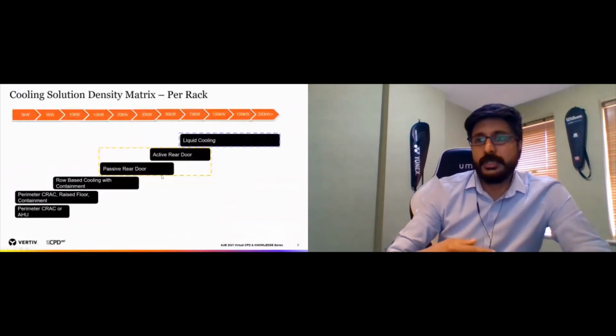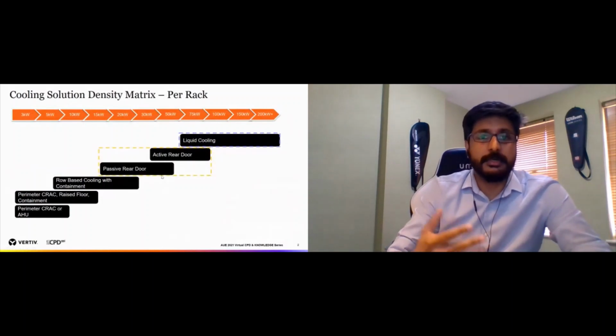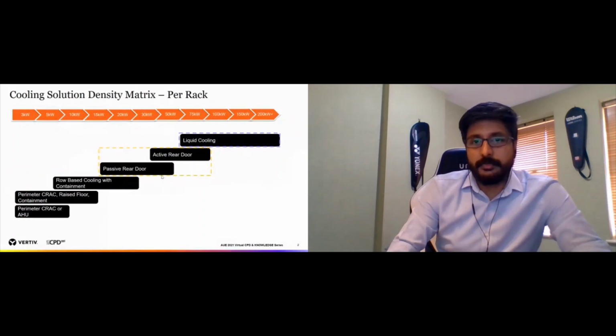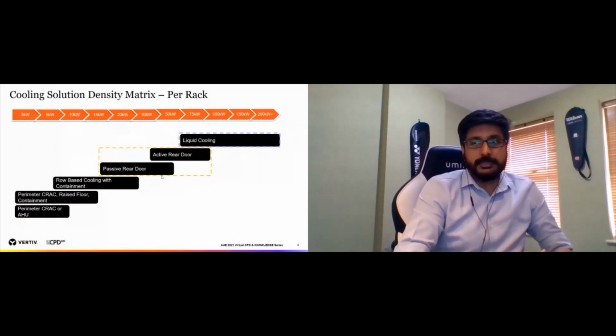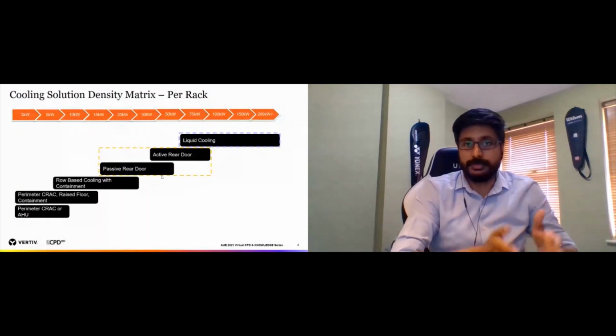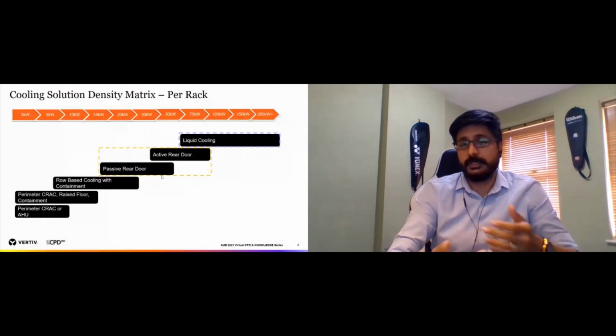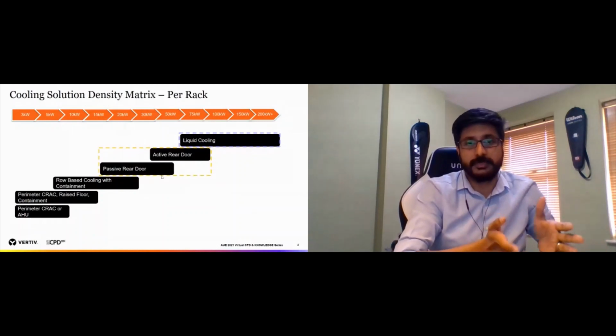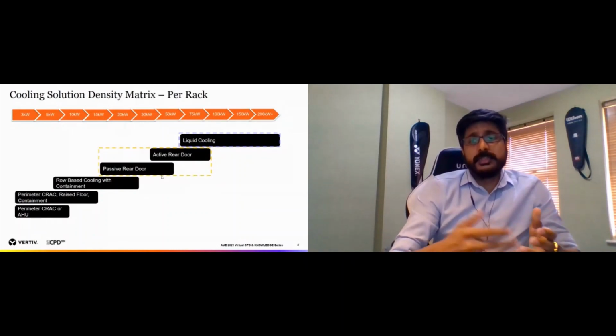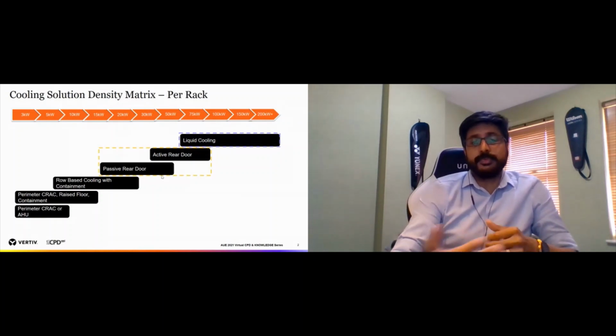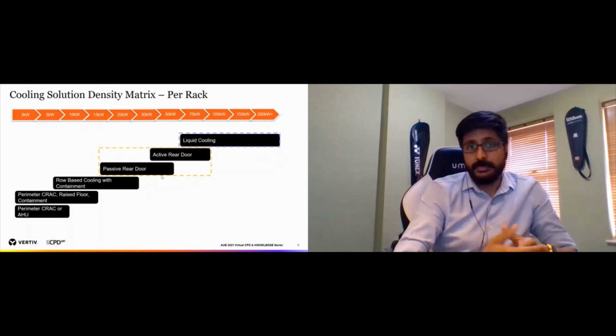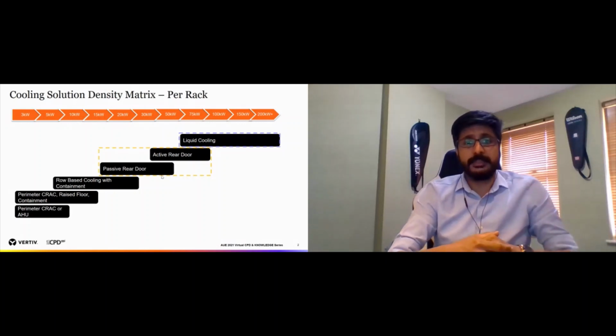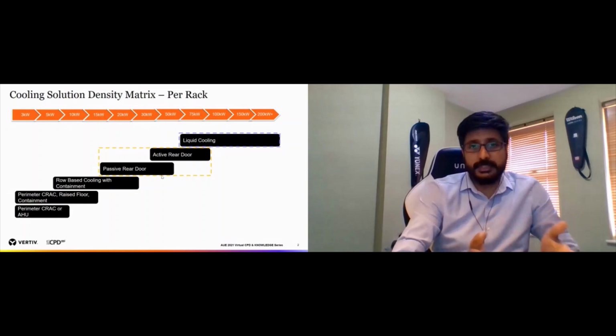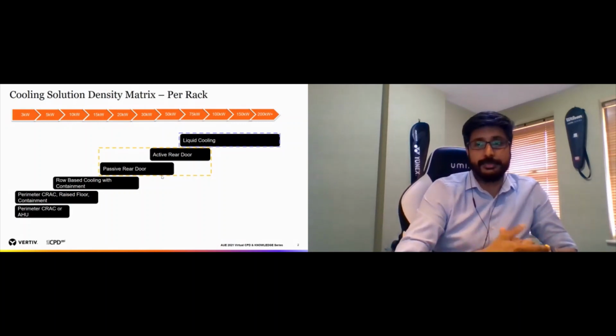As a rough calculation of how the cooling's been distributed, up to 3 to 10 kilowatts, we look into perimeter CRAC cooling solutions. Around 30 kilowatts of cooling, we think about row-based cooling, which is having a cooling solution within the row, or even against individual racks. Anything more than 30 kilowatts, say around 35 kilowatts or more, we have to look into passive rear door cooling. More than 35, say around 50 kilowatts, and if there's a bit of heat leakage, then we look into active rear door cooling as well.